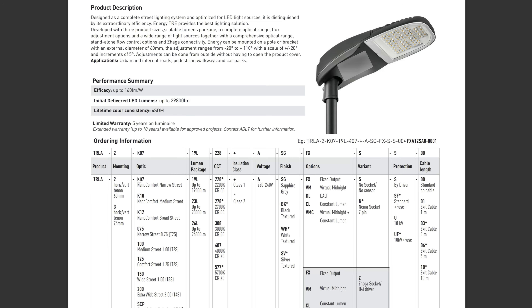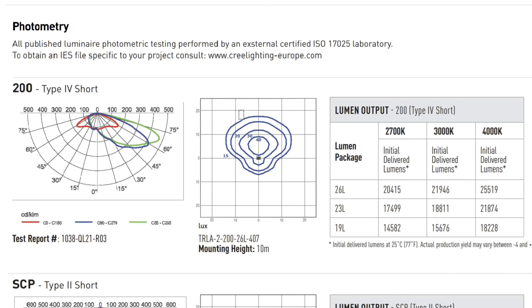The next thing we have to do is to select the light fitting. This light fitting has different optics such as narrow, wide and extra wide. I will choose the extra wide one. Also, I will choose the one with 23L, which is a 157 watt light with 21,500 lumens. 4000K is the color temperature with CRI 70. We will set the maintenance factor in Dialux Evo to 0.8. This is the photometry of the light fitting we have selected.